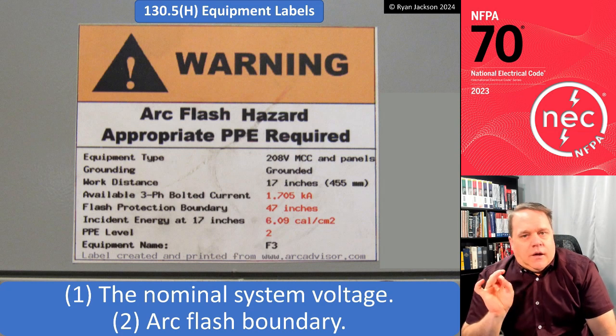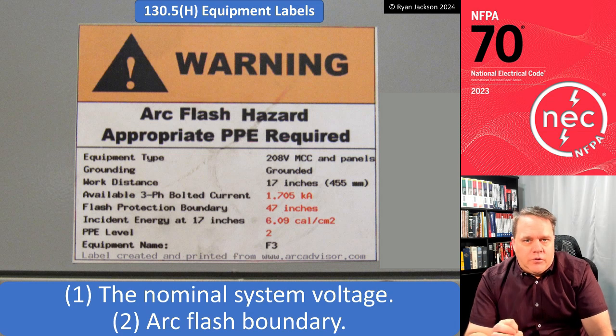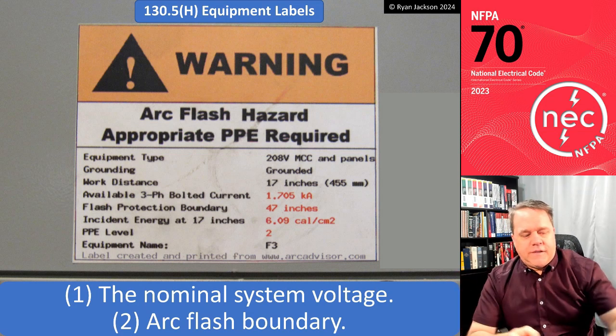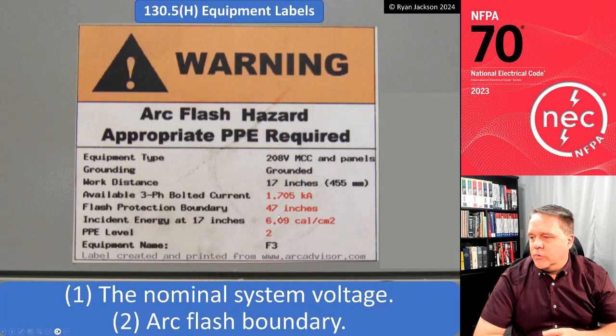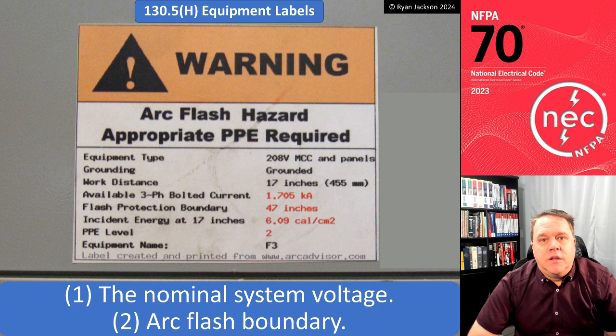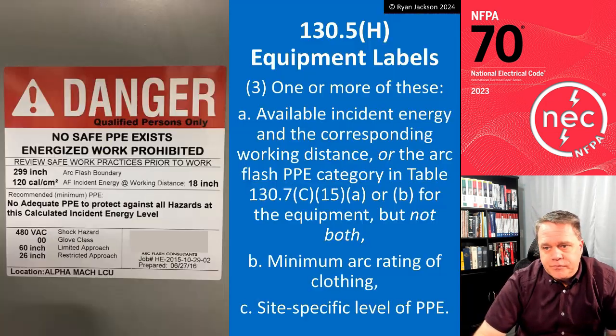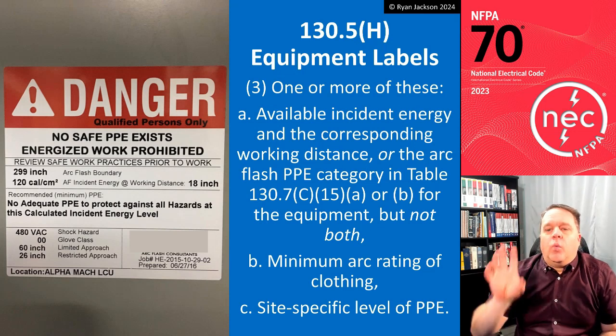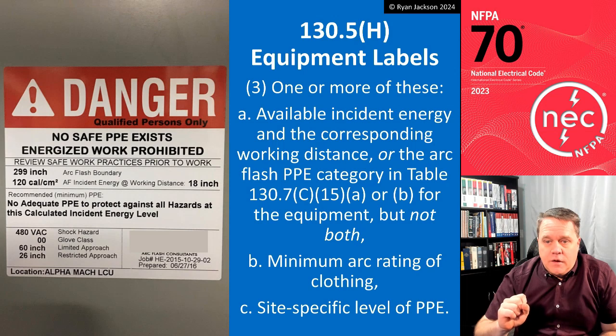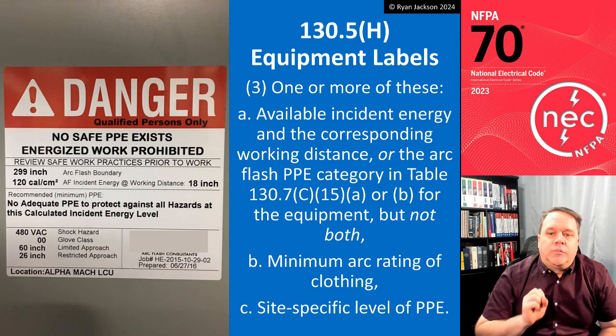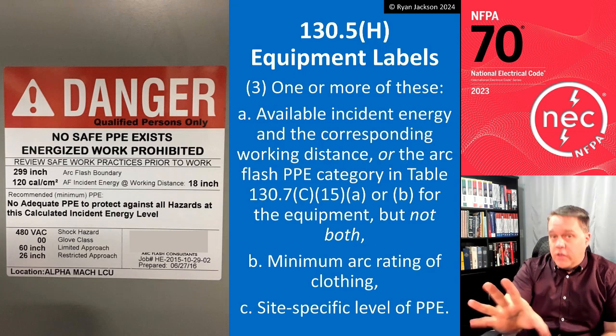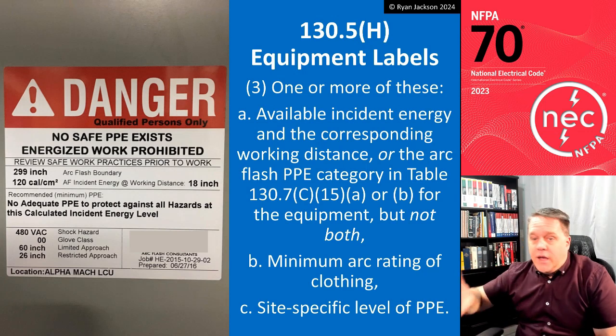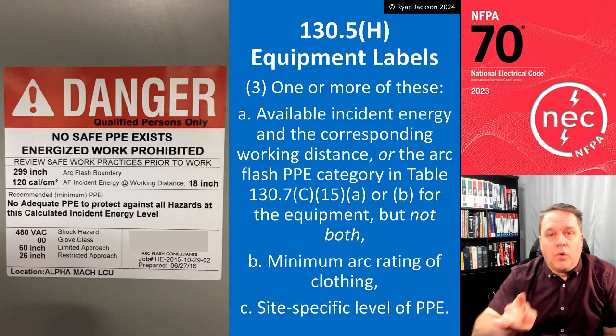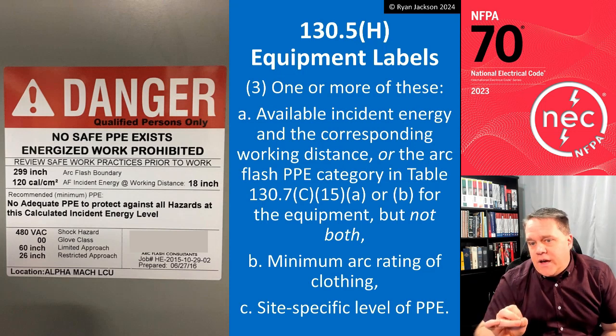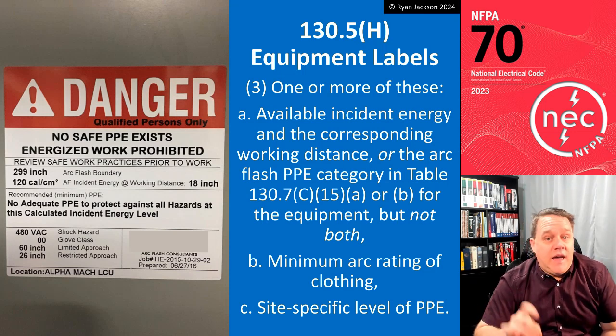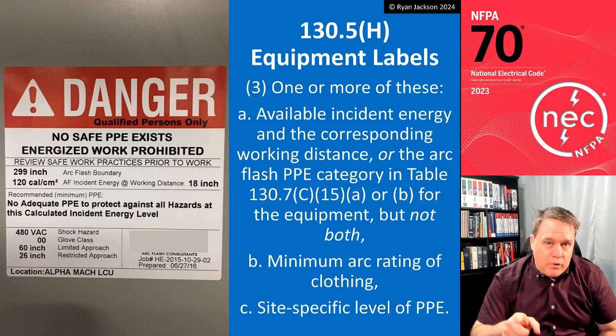Know the voltage. Number two, always have to have the arc flash boundary. Always. So this tells me that the arc flash boundary is what? 47 inches, which means I need arc flash PPE if I'm within 47 inches of the arc flash source. Item 3, I can have one or more of these. Option A, I can have the available incident energy and the corresponding working distance. Okay, which means you went through and you did the calculation. So item A, the incident energy and corresponding working distance, or the arc flash PPE category in Table 130.7(C)(15)(A) or (B) for the equipment, but not both. You're going to do one or the other.